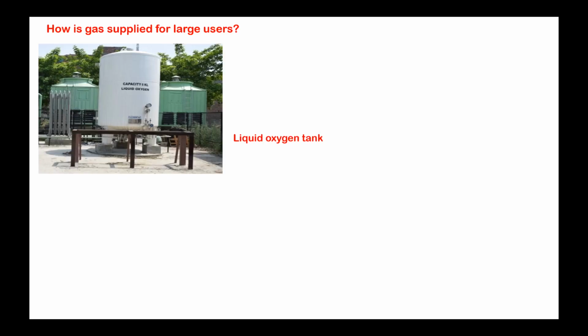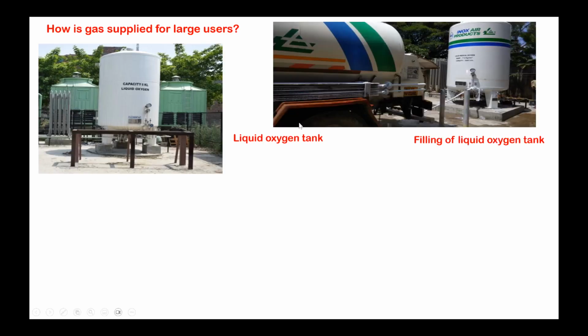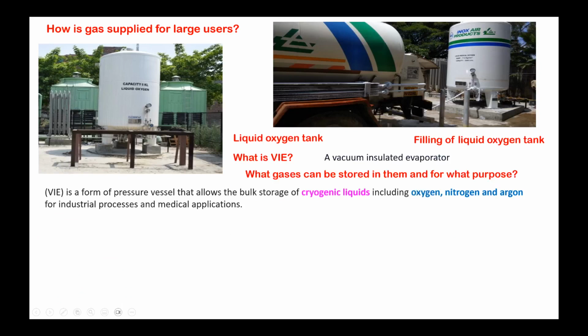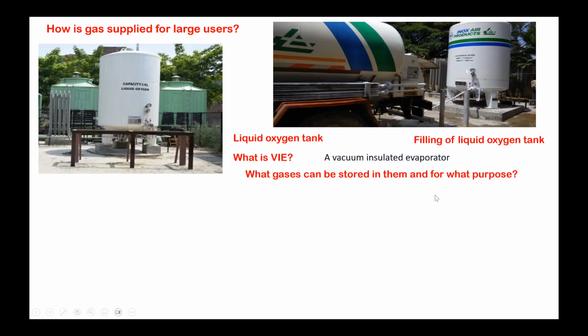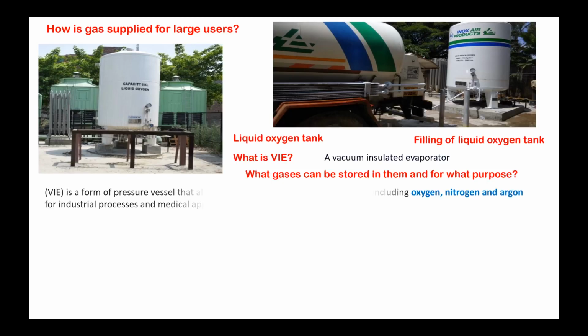Large gas supplies use the liquid oxygen tank. Some of you would have seen this in your hospitals. This liquid oxygen tank is called a vacuum insulated evaporator. Very good. What gases can be stored in them and for what purpose? Oxygen, nitrogen, and argon. Apart from oxygen, you can store nitrogen and argon also, especially for industrial purposes, but for medical purposes we usually store oxygen.